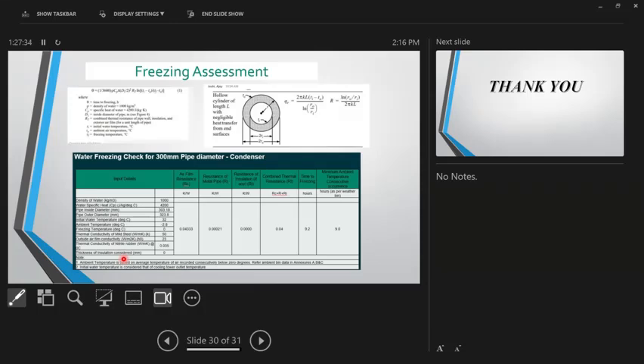So how do we do the freezing assessment? Again, there is a formula in AECOM. Don't worry much about this formula. What it does is show you the time to freeze, based on your inside diameter, the chilled water temperature or hot water temperature, and the ambient temperature. This is an example for a 300 mm pipe. What is important to know is that this formula will give you the freezing time. So for this given set of conditions, this particular 300 mm or 310 mm pipe will take 9.2 hours to freeze.